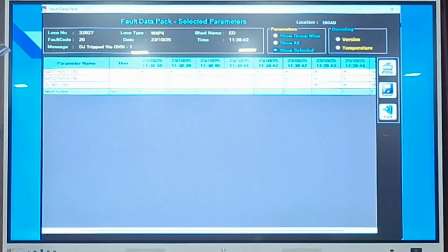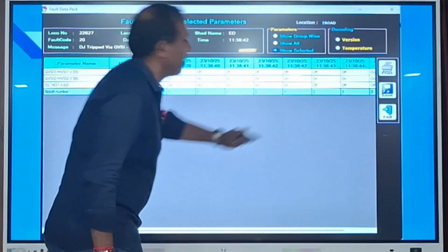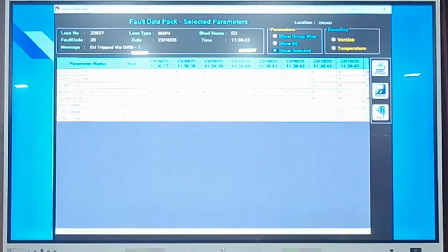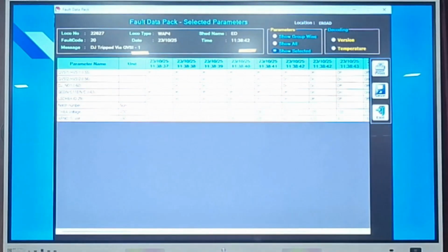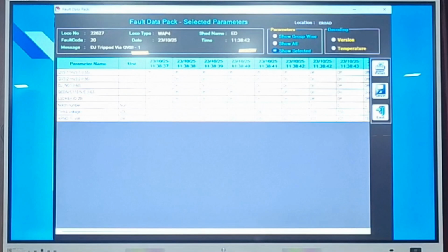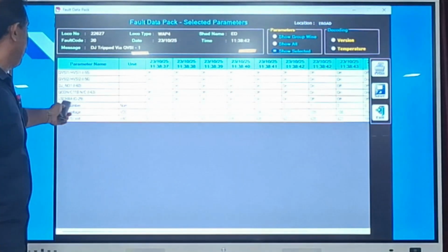So that is correct, as per logic. OVSI is tripped, DJ has been tripped, and the driver has taken notes. Before taking notes, the driver has to ensure that SIV has been picked up or not. How will he know whether SIV has picked up? Through the LSAP indication. So we have to check whether this LSAP has been extinguished or not. At this instant it has been extinguished.